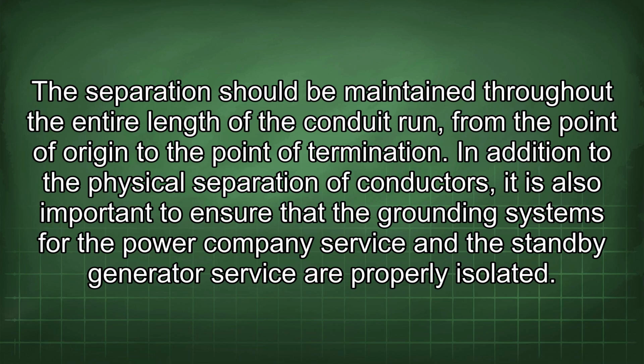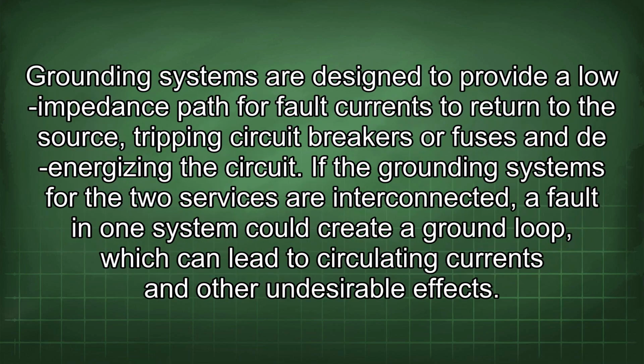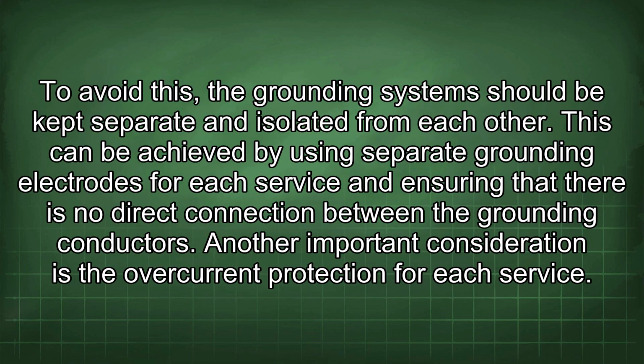In addition to the physical separation of conductors, it is also important to ensure that the grounding systems for the power company service and the standby generator service are properly isolated. Grounding systems are designed to provide a low impedance path for fault currents to return to the source, tripping circuit breakers or fuses and de-energizing the circuit. If the grounding systems for the two services are interconnected, a fault in one system could create a ground loop, which can lead to circulating currents and other undesirable effects. To avoid this, the grounding systems should be kept separate and isolated from each other.